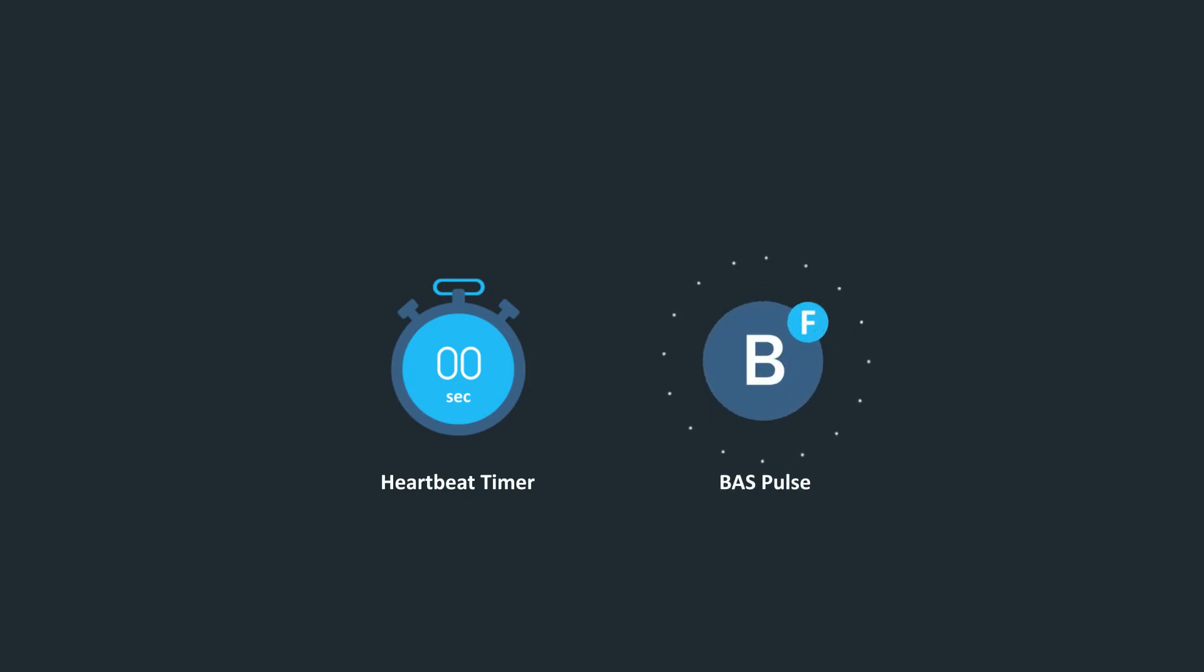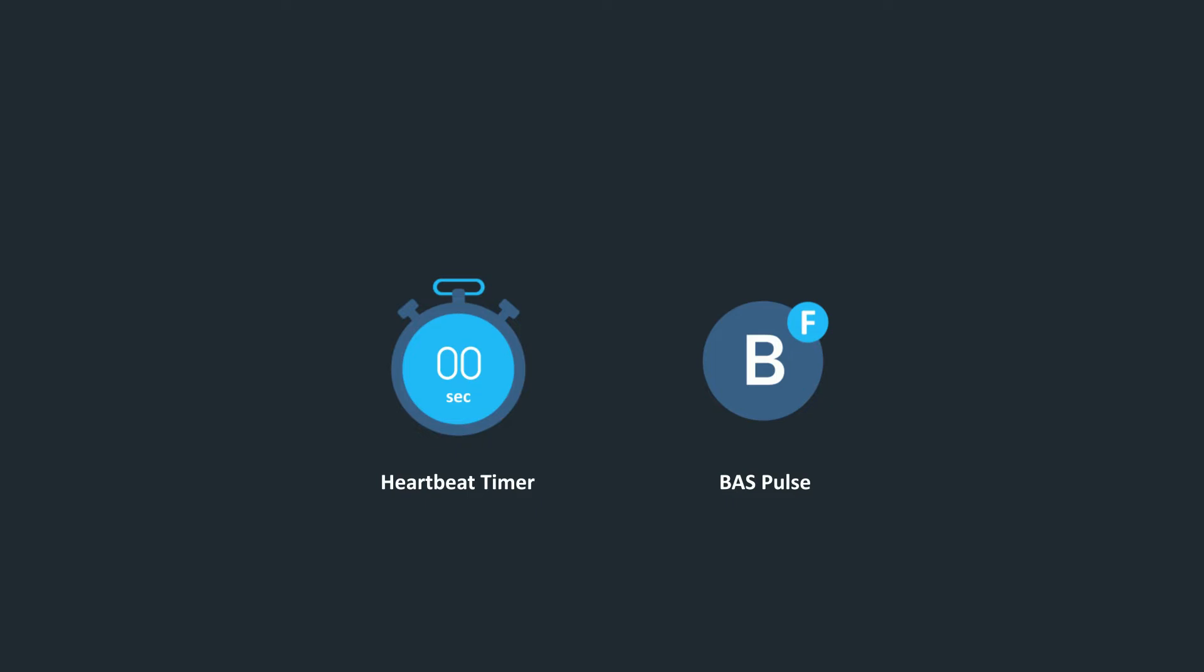For this program, we recommend using a timer and a boolean variable named BASPulse. Program your heartbeat timer to continuously count to a specified value. We recommend 30 seconds.